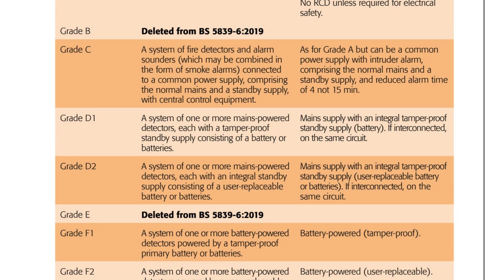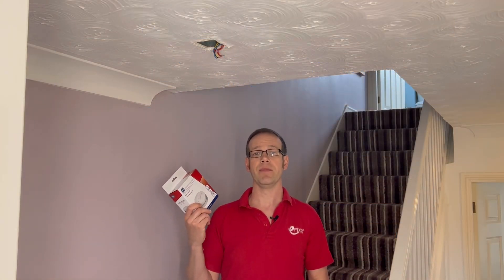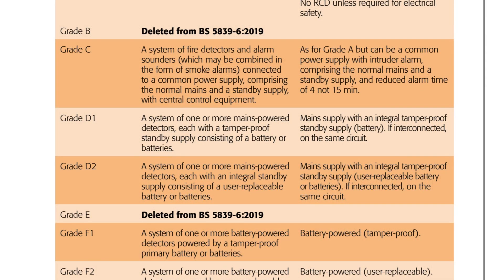Next is the Grade D system, which splits into two parts: D1 and D2. A D1 system is defined as a system of one or more mains-powered detectors each with a tamper-proof standby supply consisting of a battery or batteries. So now we're in the realm of a typical domestic fire alarm system. The D2 system is similar — a system of one or more mains-powered detectors each with an integral standby supply consisting of a user-replaceable battery or batteries.